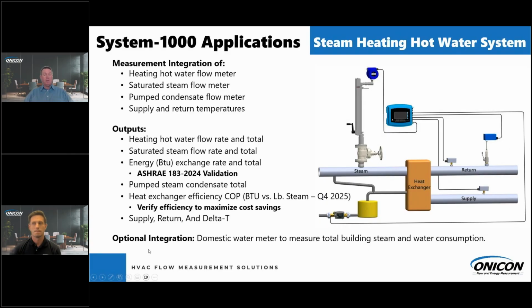You'll have outputs to your building monitoring system of heating hot water flow rate in total, saturated steam flow rate in total, the energy exchange rate and total in BTUs. Again, that'll help you with your ASHRAE 183 validation. You'll have a pump steam condensate total, and then you'll have your heat exchanger efficiency starting in Q4 of 2025. We're going to be adding that function as well, where you can do BTUs of the heat exchanger versus the pounds of steam entering it. Again, you'll use that to verify your efficiency and maximize your cost savings.